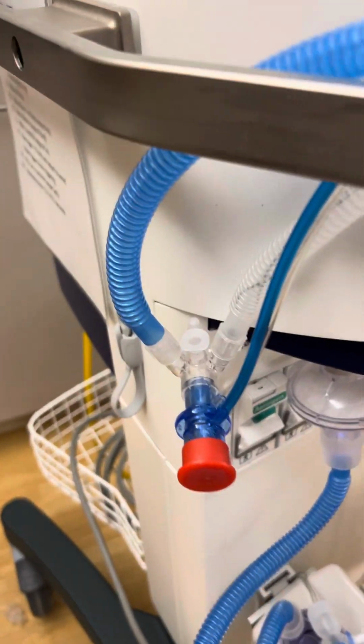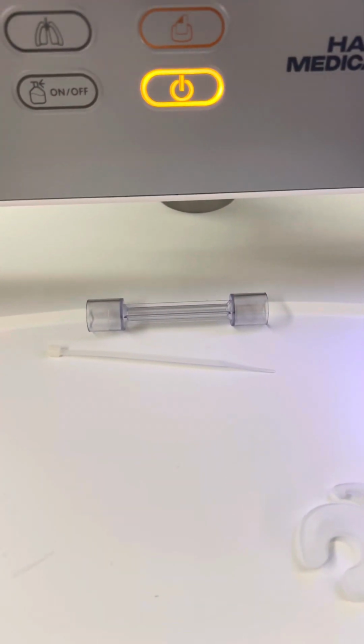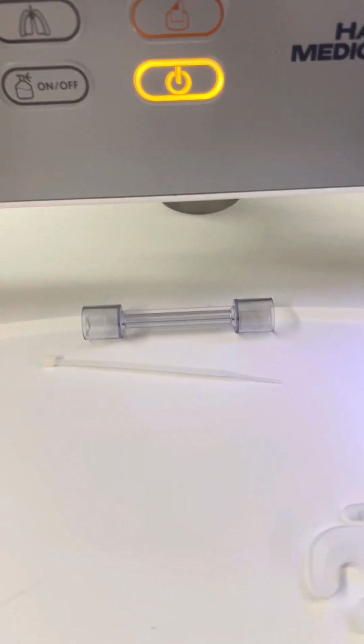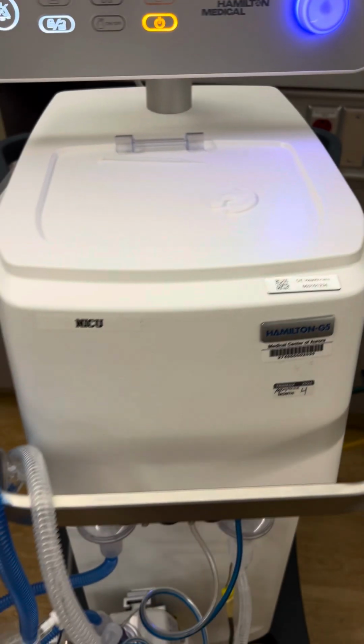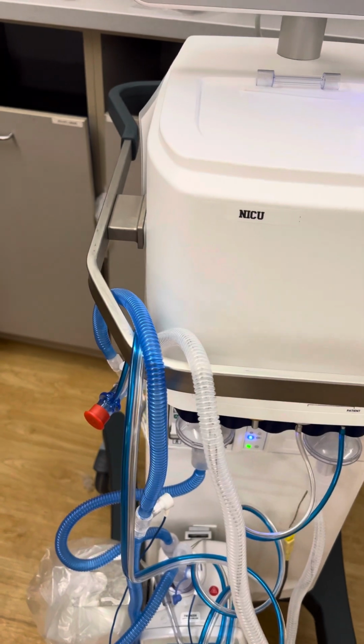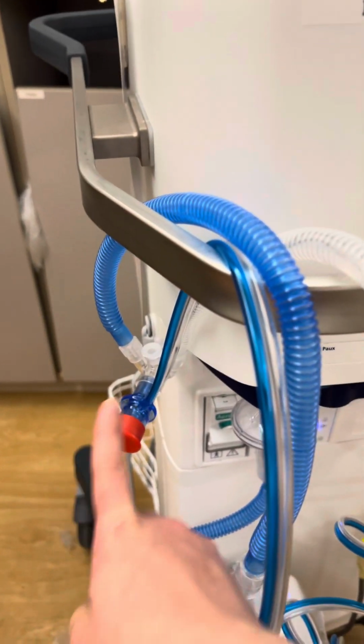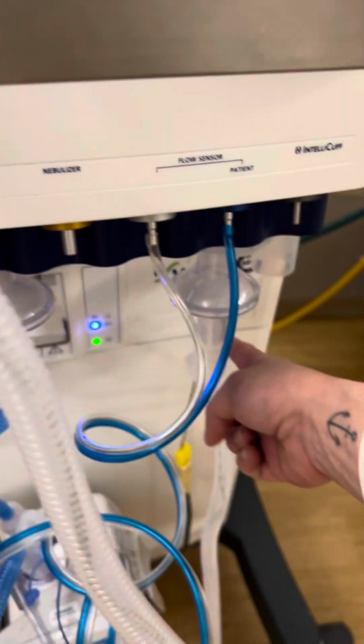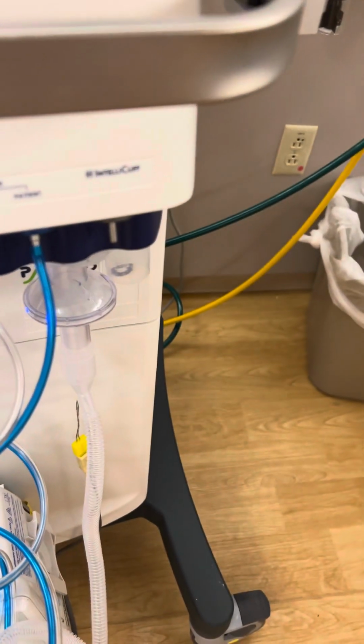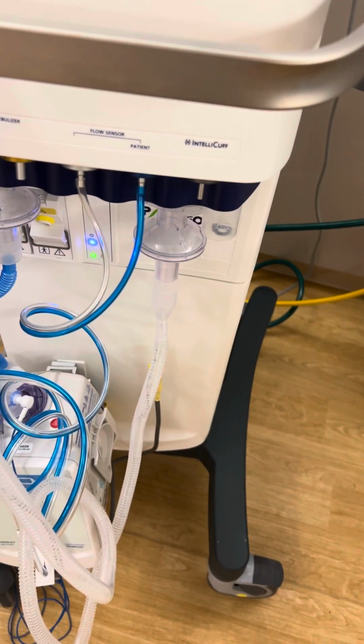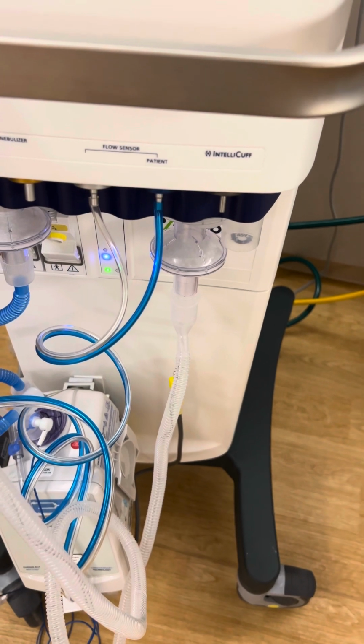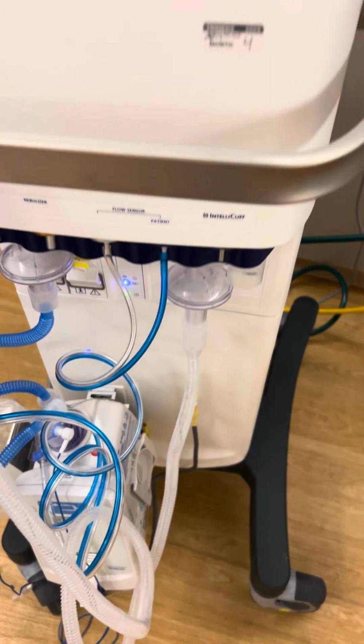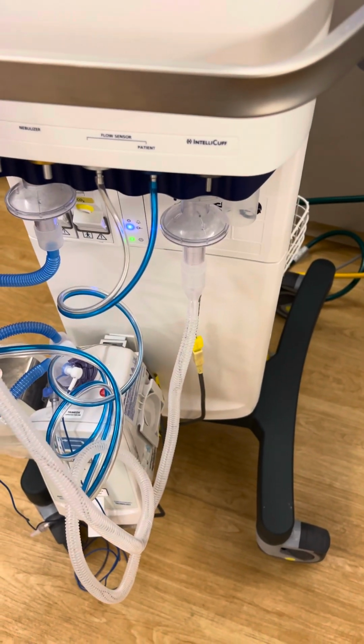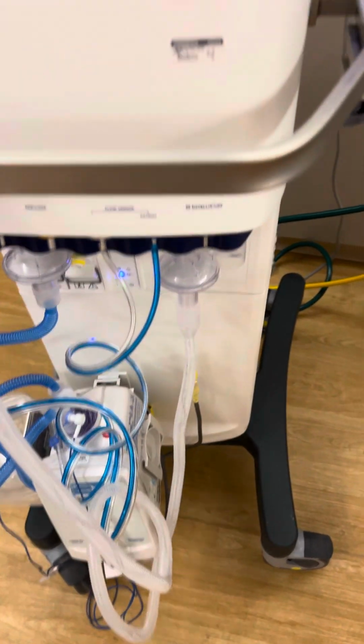In terms of the circuit, the flow sensor looks just like the other one except it's smaller. And then the little adapter to do the flow sensor check is skinnier and longer. One reminder, if we were going to put the baby in RAM in the nasal CPAP mode, we would just want to move the flow sensor from up here to down here. It's just a little too sensitive in that mode, so we're going to be measuring exhaled tidal volumes. So we're putting it on the expiratory side there. If you do move it to that side, you just want to do another flow sensor check on it.